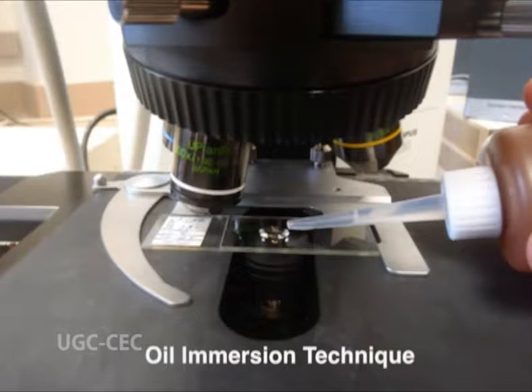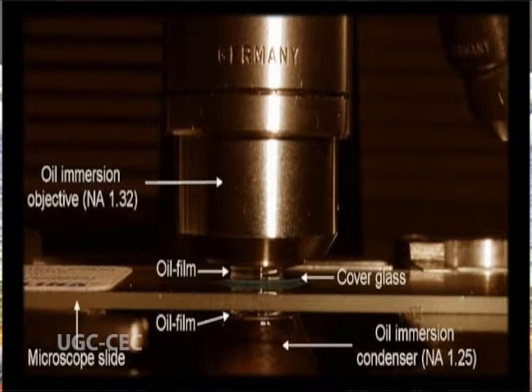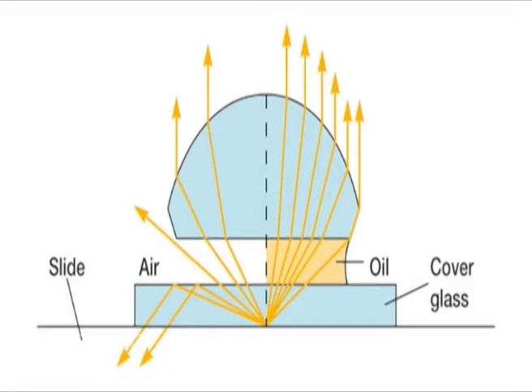The resolving power of a microscope is a function of the wavelength used and the numerical aperture of the lens system. In light microscopy, oil immersion is a technique used to increase the resolving power. This is achieved by immersing both the objective lens and the specimen in a transparent oil of high refractive index, thereby increasing the numerical aperture of the objective lens. The exact physical property of the medium through which light passes determines the amount of diffraction. With non-immersion or dry objectives, there is an air gap between the front lens of the objective and the top surface of the cover slip.